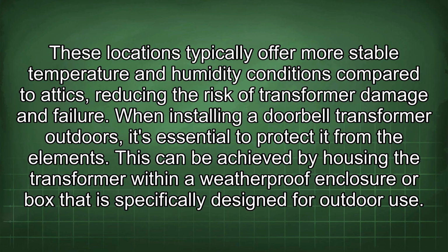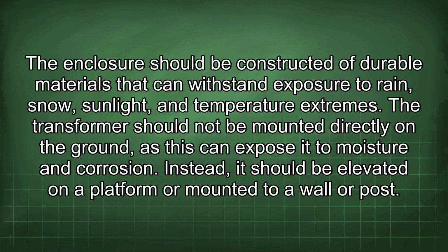This can be achieved by housing the transformer within a weatherproof enclosure or box that is specifically designed for outdoor use. The enclosure should be constructed of durable materials that can withstand exposure to rain, snow, sunlight, and temperature extremes. The transformer should not be mounted directly on the ground, as this can expose it to moisture and corrosion. Instead, it should be elevated on a platform or mounted to a wall or post.